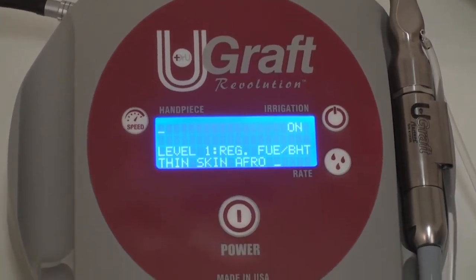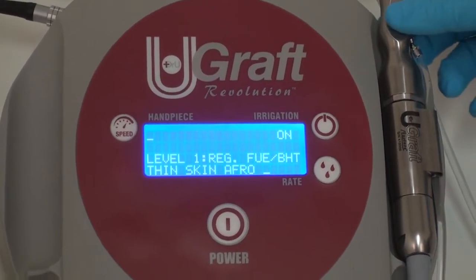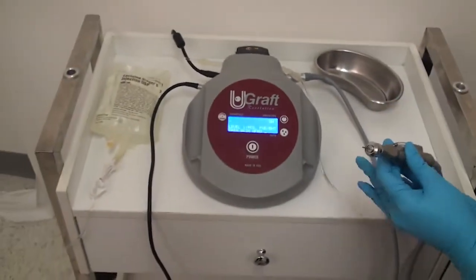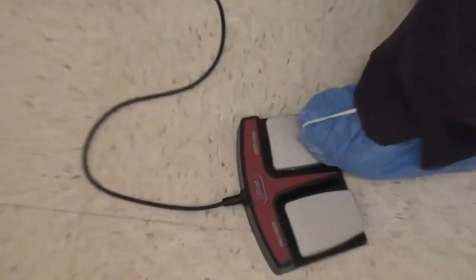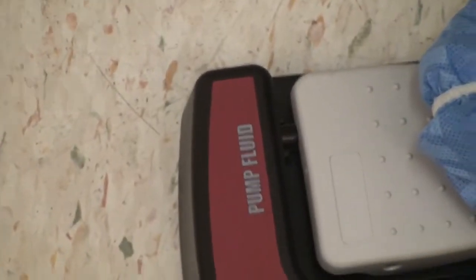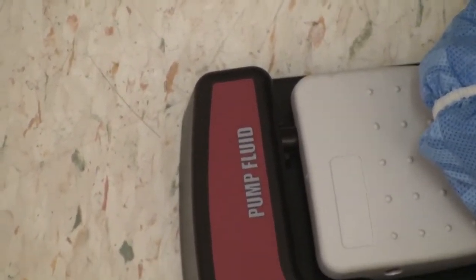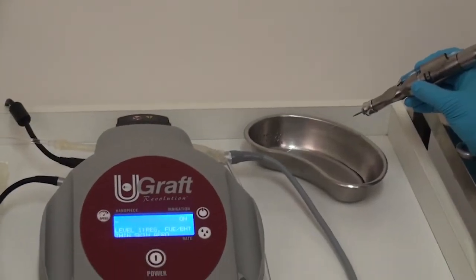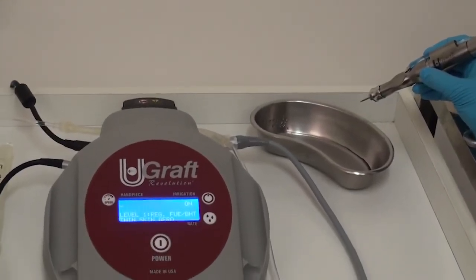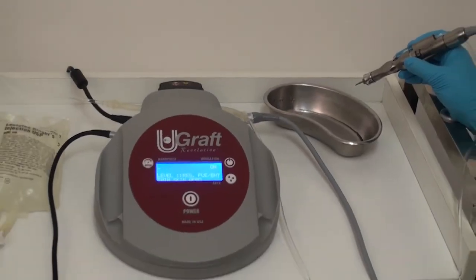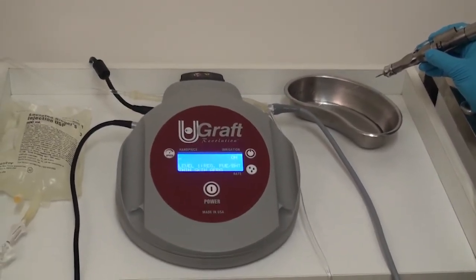Next, you would want to flush the system, which you would do by using foot pedal. Specifically, you would use the fluid pump pedal, which is the one on the right side. You would press it to eject fluid through the punch as shown here. It is very important to always do this before operating the system.